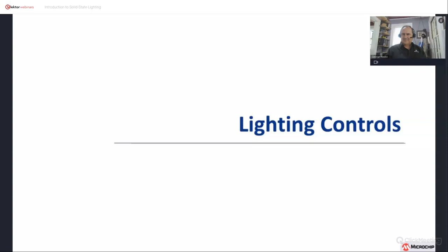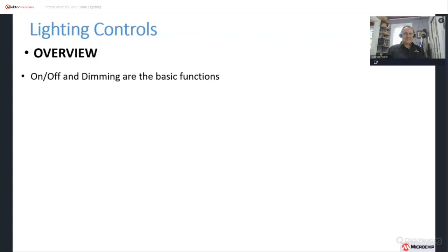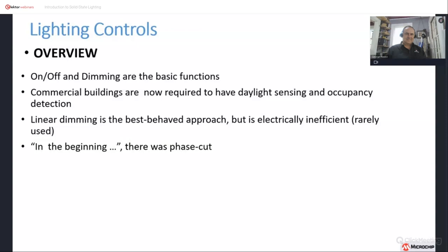Now let's talk about lighting controls — another very large topic, so this will be a high-level look at what's available. The basic controls in lighting are on/off and dimming. Nowadays, commercial buildings in California are required to have daylight sensing, which reduces lighting levels when daylight comes in through windows, and occupancy detection, which means conference rooms cannot have lights left on for long periods when no one is inside.